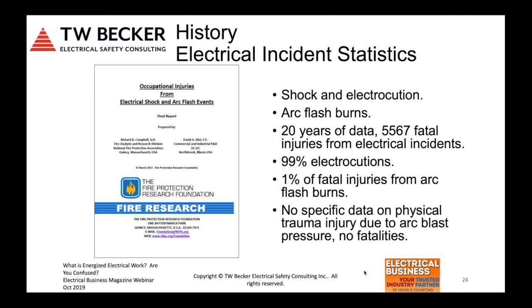There's no specific data on physical trauma injury due to arc blast pressure. And as far as I can tell, there's no fatalities occurring due to physical trauma from arc blast pressure. And this is important when we do a risk assessment and we look at potential injury or damage to health, and we look at the arc blast hazard, which is one of the myths and misinformation that's been occurring in the last 10 years about arc flashes, specifically, the arc blast secondary effect on the worker.